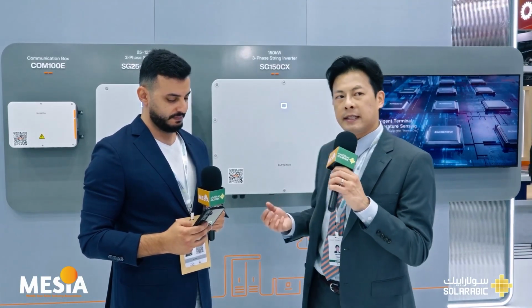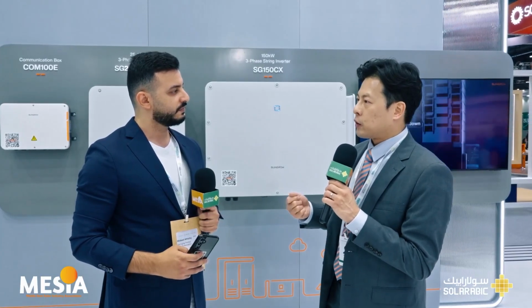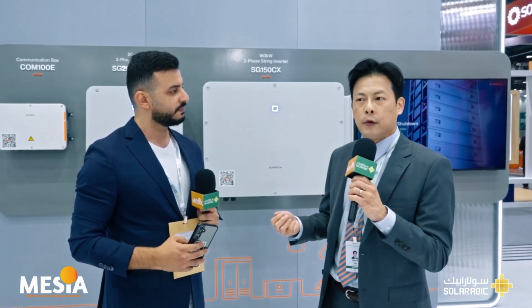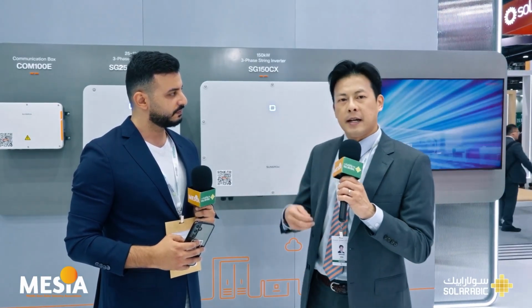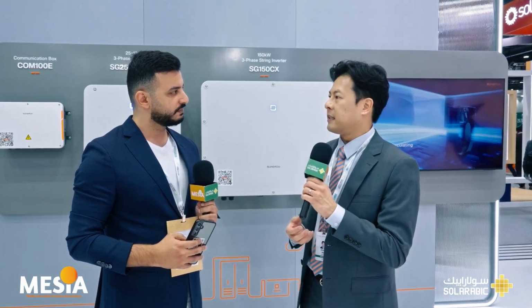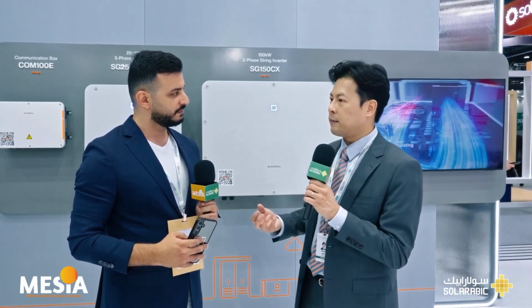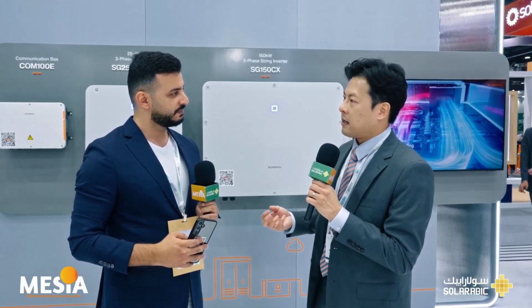Thirdly, from the practical side, we have implemented this technology in the Middle East. In one of our recent projects, which is a 1 gigawatt project, we used this technology to commission the project without the actual grid support and also without voltage from the grid. We used this black start technology to energize the local network and start the commissioning even before the commercial COD time.